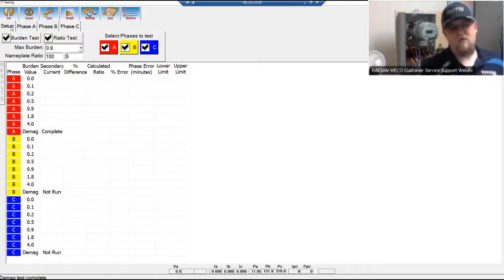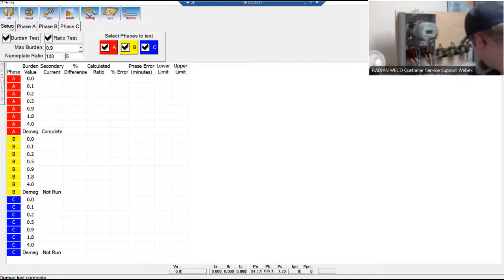So now we want to get the primary measurement going. For that, I have this SR704 clamp of ours. This is a clamp style probe that just clamps onto the primary. A lot more common ones as well are rope probes, sensor link probes, things like that to also get in the primary. Any one of those will work, but because of the size of my setup here, I've got a clamp to do that. These clamps for the RW plug into the A phase input only.